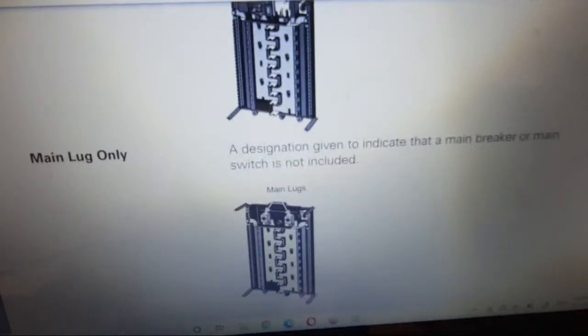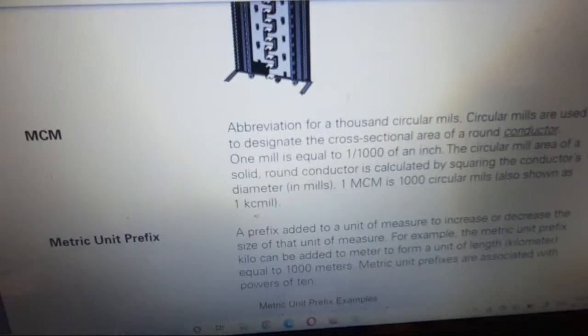Main lug only: a designation given to indicate the main breaker or main switch is not included. MCM: abbreviation for 1,000 circular mils. Circular mils are used to designate the cross-sectional area of a round conductor. 1 mil is equal to 1/1,000 of an inch. The circular mil area of a solid round conductor is calculated by squaring the conductor's diameter. 1 MCM is 1,000 circular mils, also known as 1 kcmil, or 1 kilo circular mil.